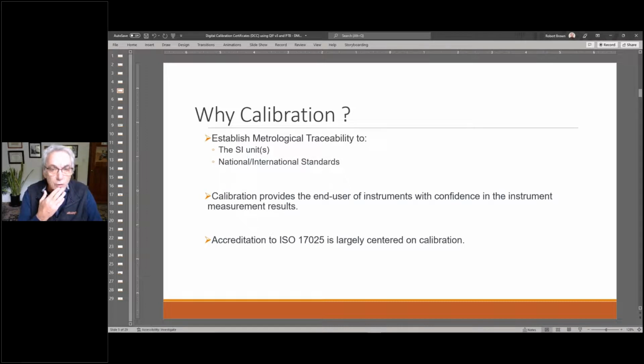Again, it is about traceability. It is about a certificate chain. It is traceable to the Standards International units, and it provides an end user with the confidence of the instrument measurement results. There's an ISO standard that governs the operations and process and procedures of calibration labs, known as ISO 17025, and all major labs get accredited to this standard.